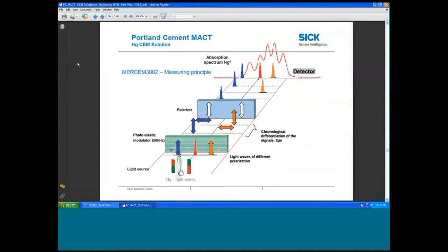And the measurement principle is also a little bit unique compared to other mercury monitors. We're utilizing an effect called the Zeeman effect, where we've got a mercury light source around which we supply a magnetic field. And what the magnetic field then allows us to do is to split the initial light wave into two separate beams of opposite polarizations. And by putting them through some optics, this photoelastic modulator and polarizer, we're able to generate alternating reference and measurement signals on a time scale of about 2 microseconds.